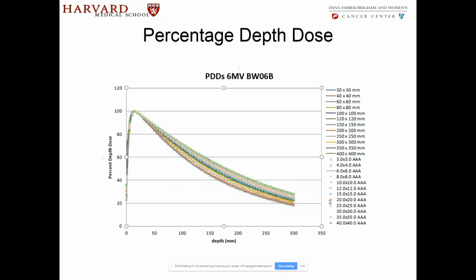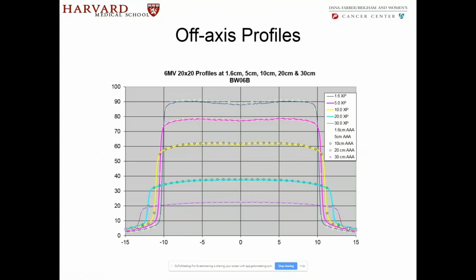I'm showing just PDDs. You can see the PDDs for different field sizes. So this is for 6 MV energy. We go down to about 30 cm. And it takes a lot of time to collect all this data, but it has to be done. When you do profiles, same thing. You can see the profiles at different depths, 1.6 cm, 5 cm, down to 30 cm. You can see the spread as the beam is spreading out as it's going down into the water.